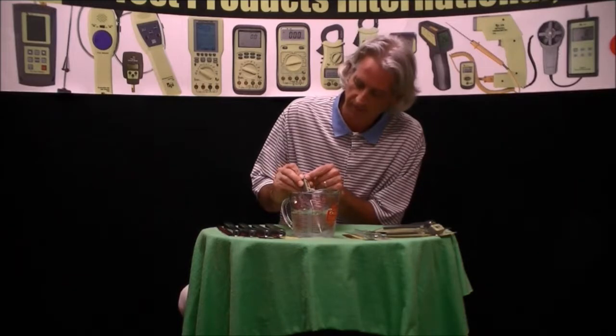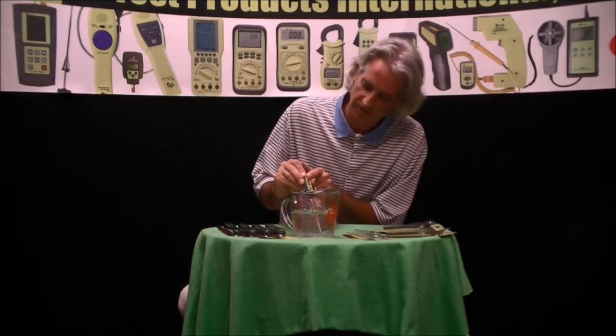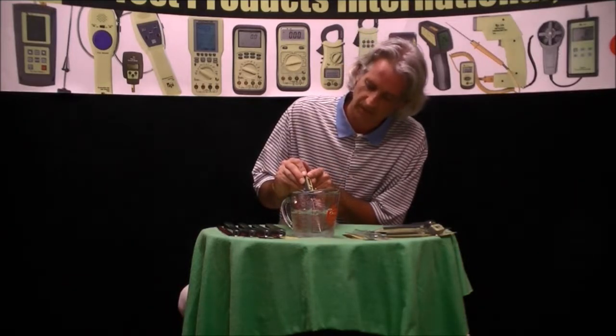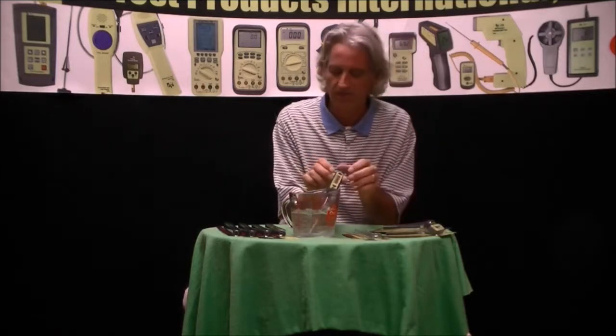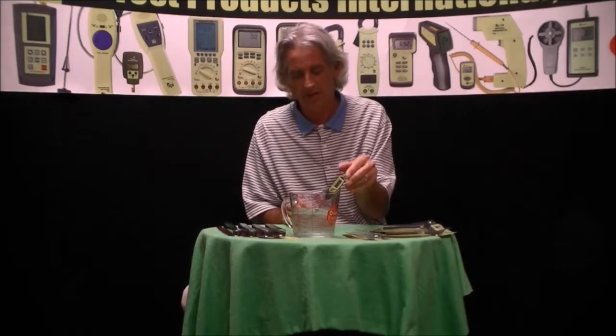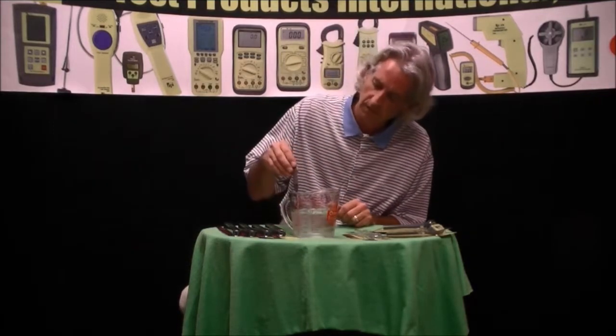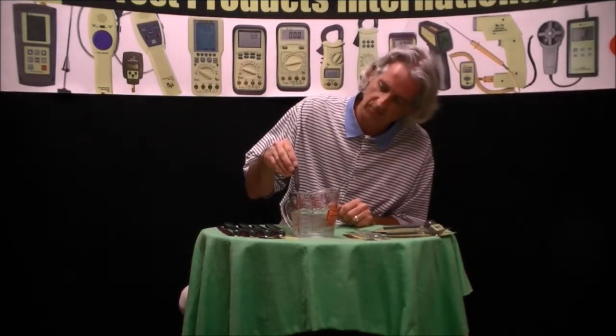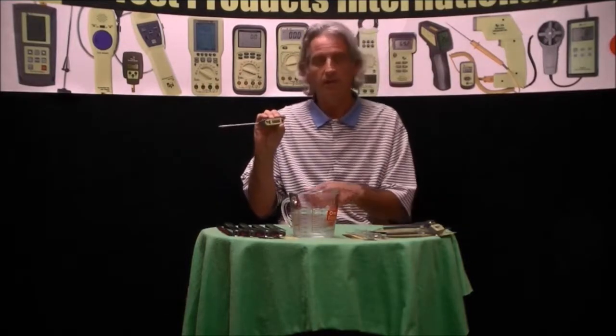So this is stabilizing about 32.6 degrees. I'm going to press and hold the data hold button approximately 8 seconds. It'll get into cal mode, and I'll see CAL flashing on the LCD screen. As soon as I have that, which is there, then I know that it's going into automatic calibration. As soon as it flashes me a temperature reading, 32 degrees Fahrenheit, then I know I've successfully calibrated the unit back to plus or minus 1 degree Fahrenheit.